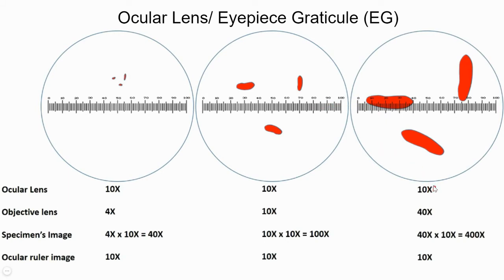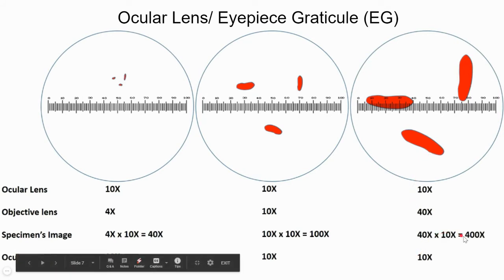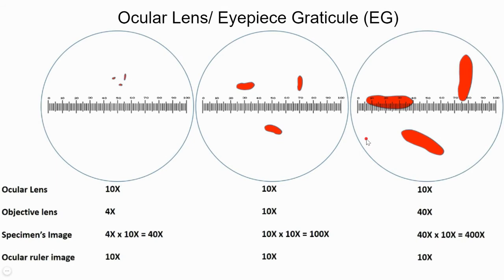In the third case, using the same ocular lens with the same eyepiece graticule, the specimens appear bigger again because the objective lens is now 40x, giving an overall magnification of 40 × 10 = 400x. Across all three cases, we notice that the specimen size increases as we increase the objective lens magnification, but the eyepiece graticule scale size remains the same throughout — because the eyepiece graticule is fixed to the eyepiece lens, which we are not changing.